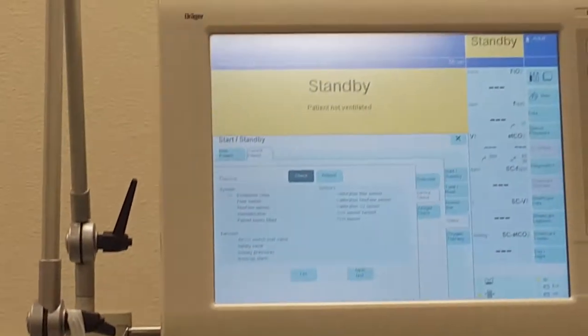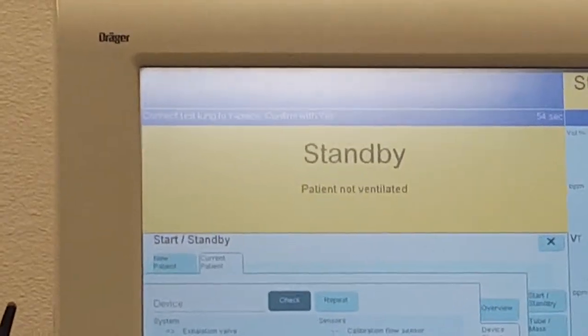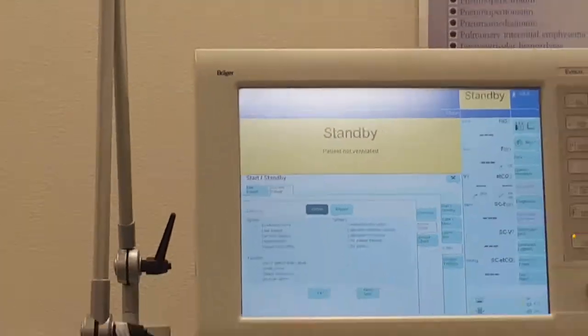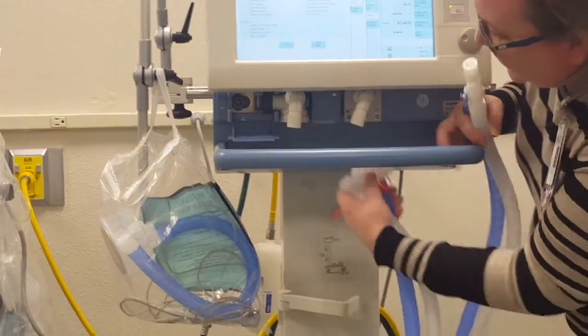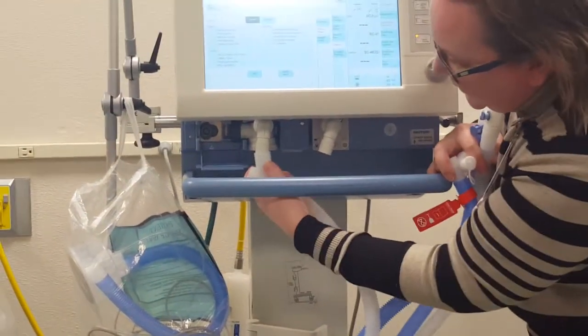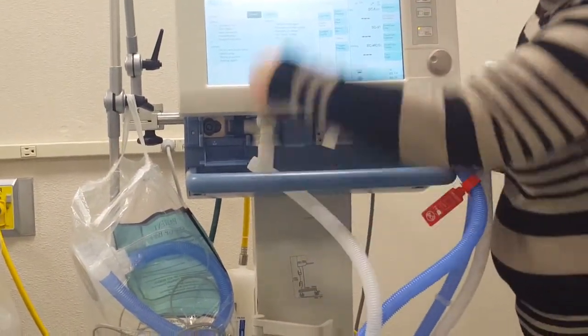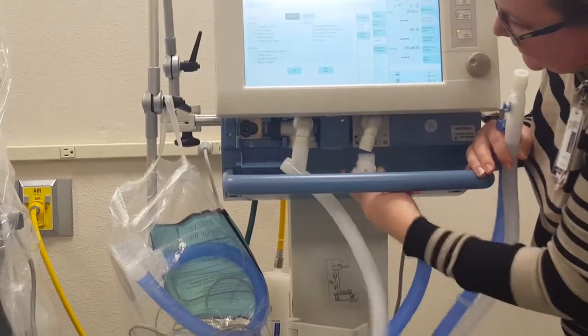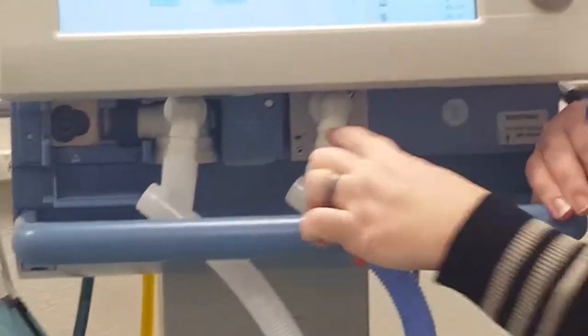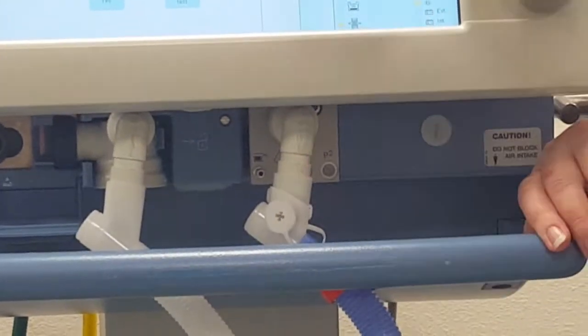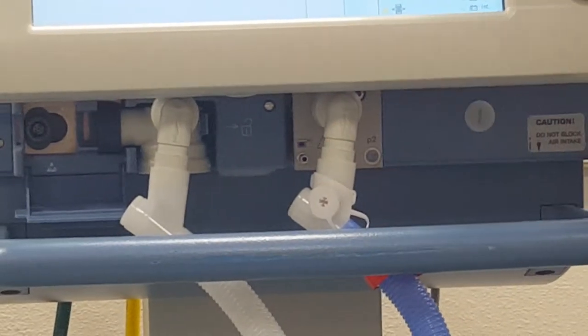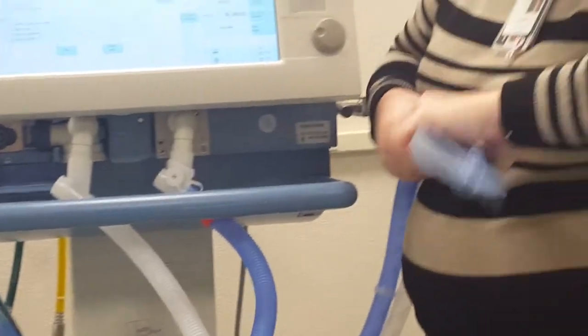Connect test lung to Y piece. So we have to make sure our ventilator is hooked up. We could have started this way. If this is the exhalation, this one goes here. It has an arrow pointing into the ventilator. This is inhalation, going to our patient, and it has an arrow pointing out. Remember, like I told you, to go to the patient. We're going to connect our test lung and then hit yes.